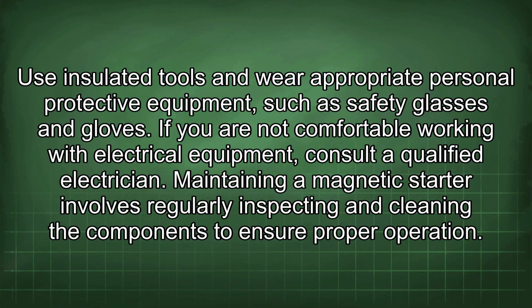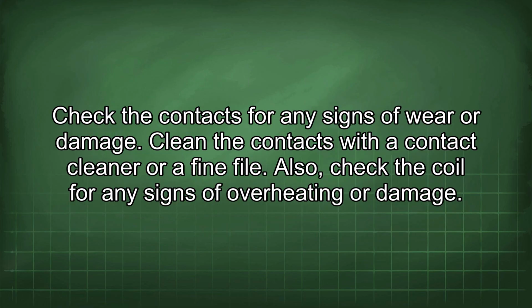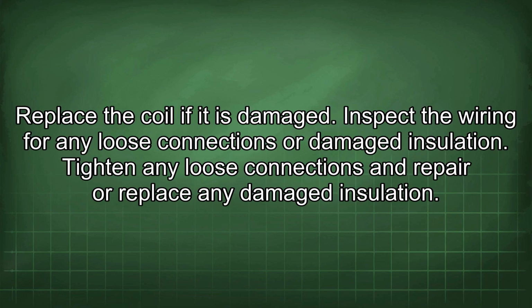Maintaining a magnetic starter involves regularly inspecting and cleaning the components to ensure proper operation. Check the contacts for any signs of wear or damage. Clean the contacts with a contact cleaner or a fine file. Also, check the coil for any signs of overheating or damage. Replace the coil if it is damaged. Inspect the wiring for any loose connections or damaged insulation. Tighten any loose connections and repair or replace any damaged insulation.